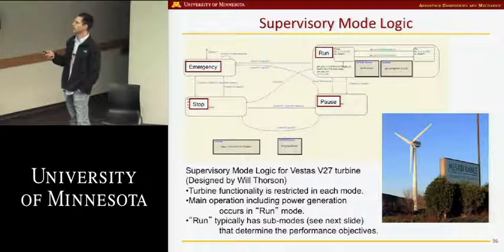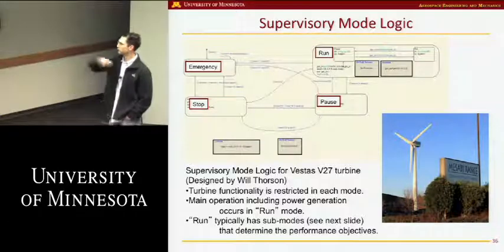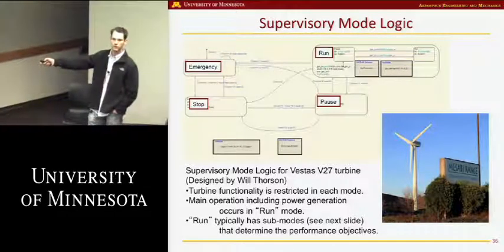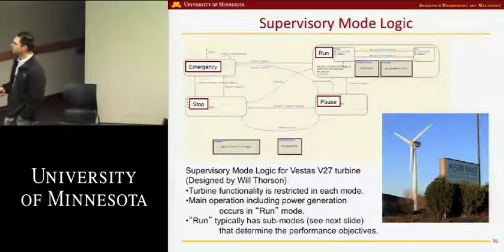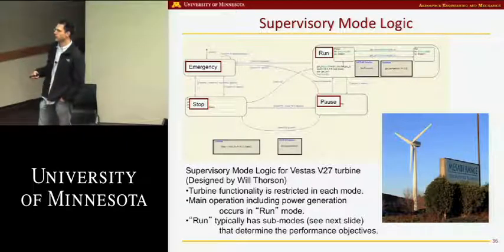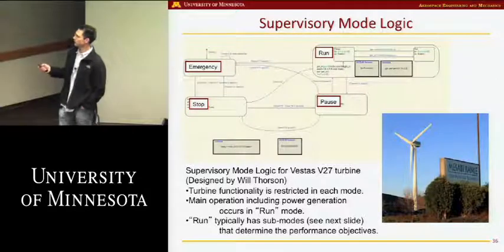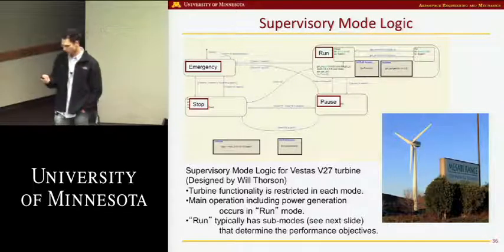If someone presses an emergency stop button while the turbine is running, it immediately transitions into the emergency state — blades move to a safe configuration, a brake is applied to the rotor, and various protective actions occur. When you turn the turbine on, you sequence through the various states and hopefully get into the run state, where the turbine starts turning the blades. Once it starts producing power at 60 Hz, you connect to the grid. What I'll tell you about for the rest of the class is what happens in this run state — actually controlling the turbine and producing power.